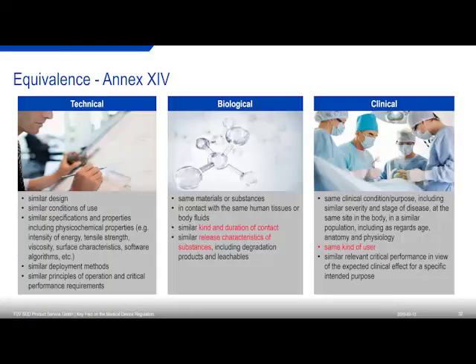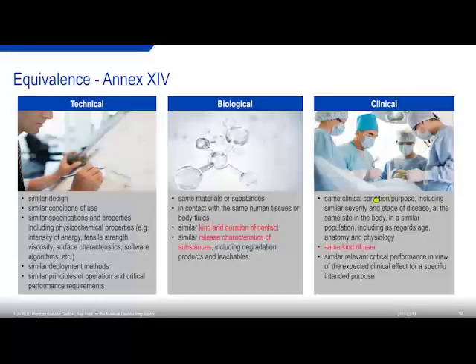So coming back to the topic of equivalence, equivalence is something that will be very, very difficult under the MDR. I am aware of the fact that a lot of devices currently on the market follow the equivalence approach. But what is equivalence actually? Equivalence was redefined in MEDDEV 2.7.1 revision 4, and I think under revision 4 it's already very, very difficult to find a really equivalent device, because it has to be equivalent on technical, biological, and clinical aspects: similar design, similar conditions, same materials, same clinical conditions, same kind of user, similar kind and duration of contact. So all these elements must be fulfilled to really talk about equivalency.